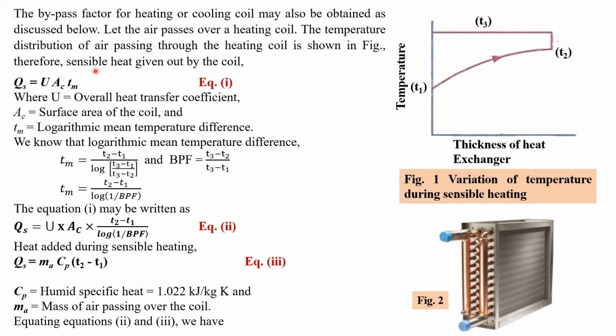Therefore the sensible heat given out by the coil is given as Qs equals U Ac Tm. This is equation number 1. Here the terms are quite important. U is the overall heat transfer coefficient, Ac is the surface area of the coil, and Tm is the logarithmic mean temperature difference. We know that for this sort of heat transfer, where one fluid simply undergoes a phase change and there is no direct mixing of the two fluid streams, steam flows through the pipeline and over these tubes the air is made to flow. For this type of heat exchanger, the logarithmic mean temperature difference is given as (T2 minus T1) divided by log of (T3 minus T1) divided by (T3 minus T2).